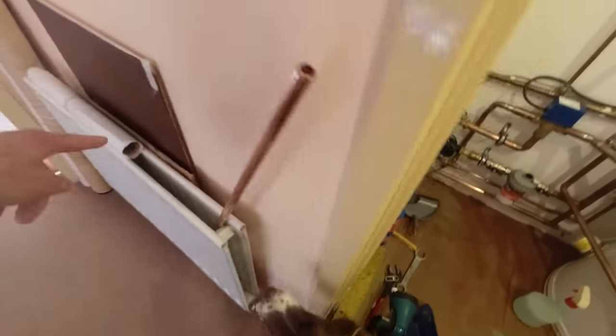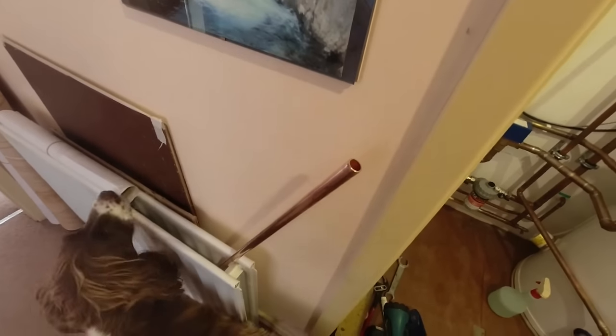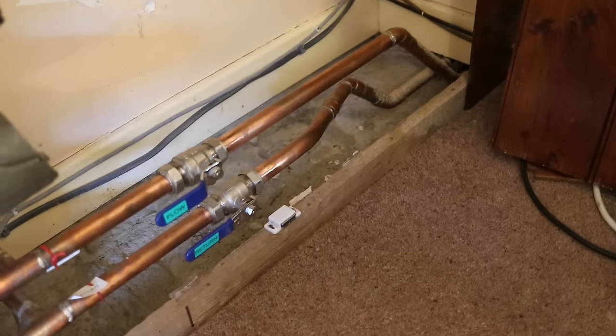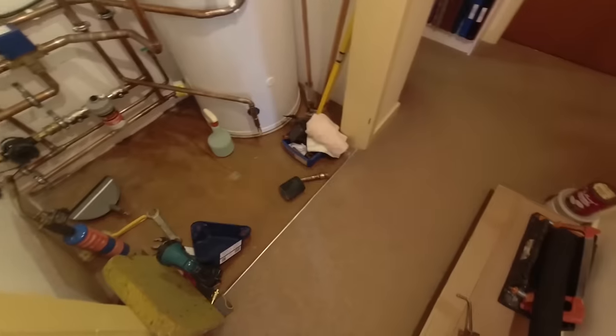If I do need to do any upgrades, it's because the existing heating system is 22mm pipes that come and split out, so half of the house runs off one leg of 15mm and the other half runs off the other leg. So we may need to upgrade the little bit that goes along here and then splits off to the bedrooms, upgrade that to 22mm because this bit here is 15. But the calculations show that it should be okay, so I thought I'd just try it and see how it goes.